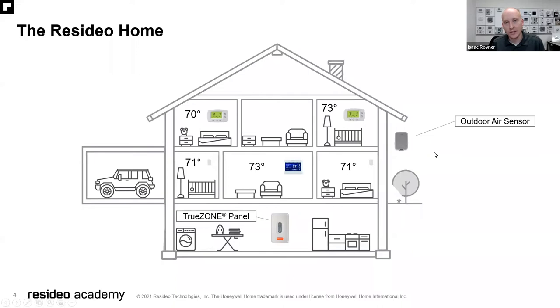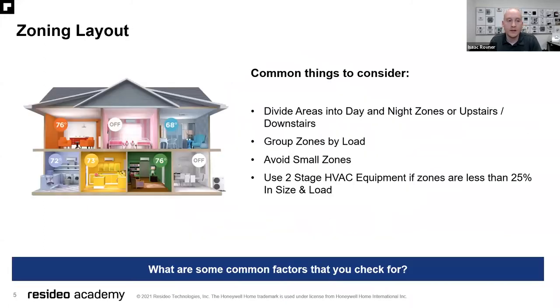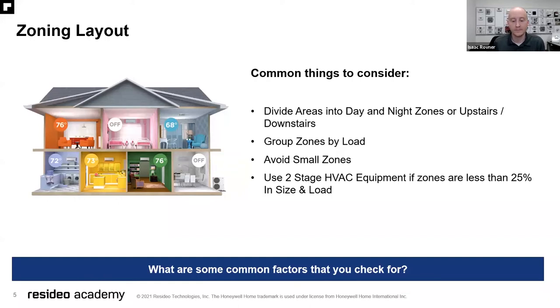Outside the house, we have an outdoor air sensor. For example, if we're using a heat pump and need control for lockouts, we can easily add that in without running any wires. When considering a home to zone out, we want to divide zones into day or night, or upstairs and downstairs, which is very common. We can group zones by load, but we want to make sure to avoid small zones. Use two-stage HVAC equipment if zones are less than 25% in size and load if possible.